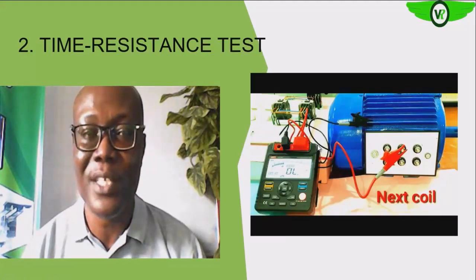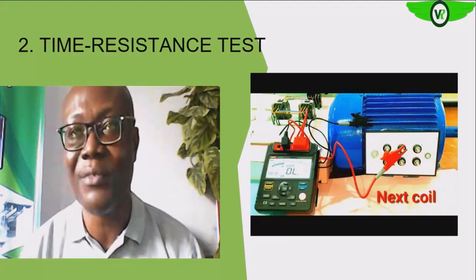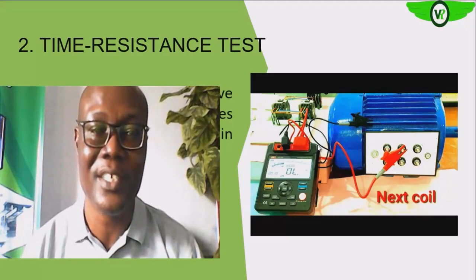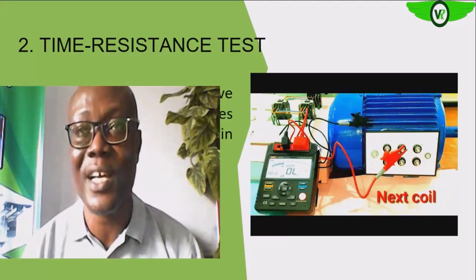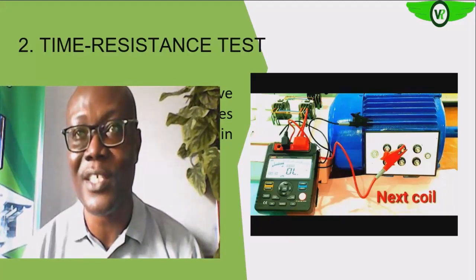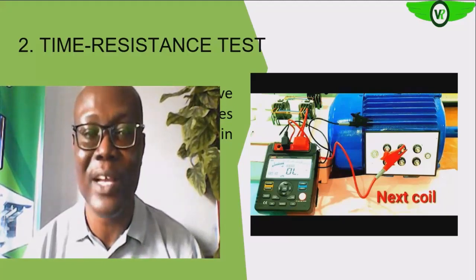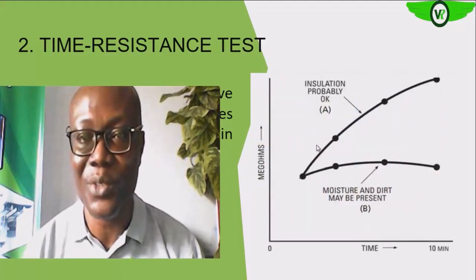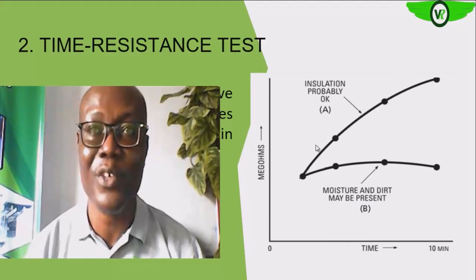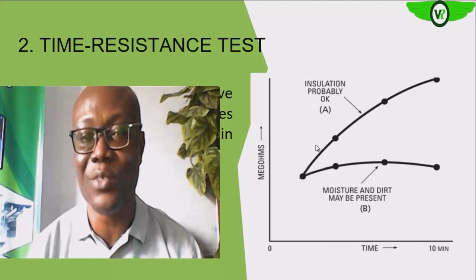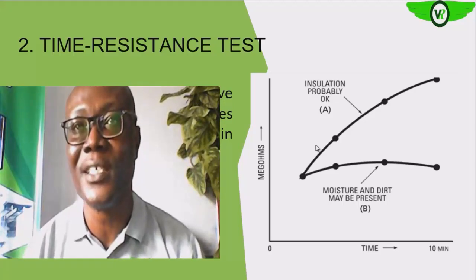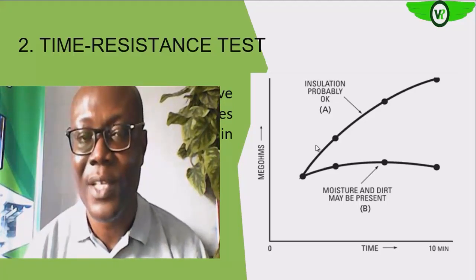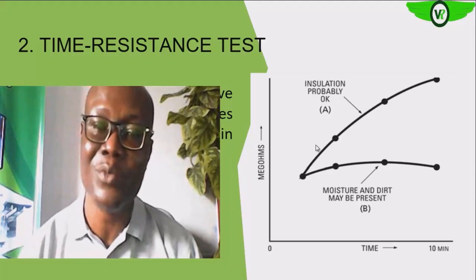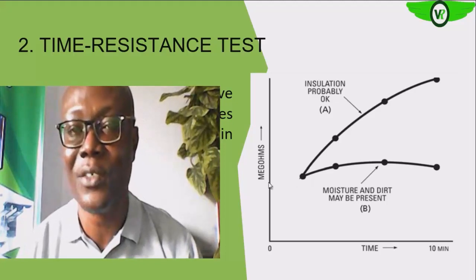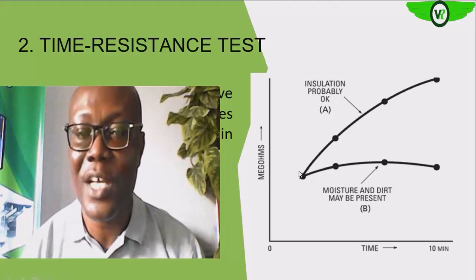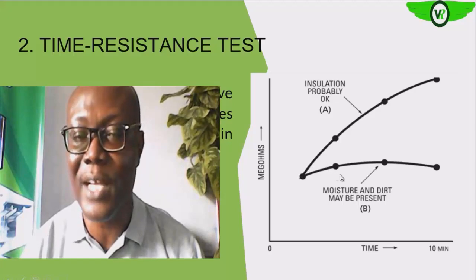So the time test, like we said, we have the dielectric absorption ratio test and we have the polarization index test. Okay, so you simply take the reading at 20 or 30 seconds and at 1 minute, and then divide for the dielectric absorption ratio test. And then for the polarization index, you take the reading at 1 minute and also at 10 minutes, and then you divide the 10 minute reading by the 1 minute reading. Okay, so here you can see your time test.